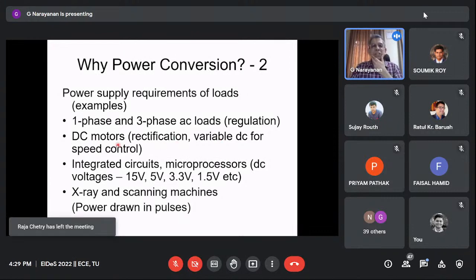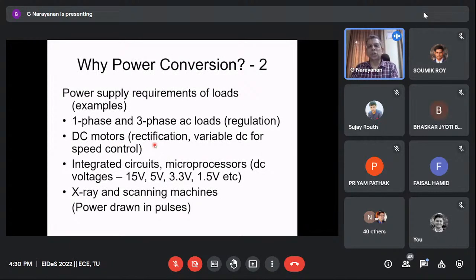That again depends. For example, if you have a 200 volt DC motor, at 200 volt it will run near full speed. At 100 volt it will run at half the speed. So you will need some variable DC for its speed control. If you want it to operate at various speeds, you will have to control the voltage also. So it's not just rectification. You need a kind of controlled rectification where you can vary the DC output also.